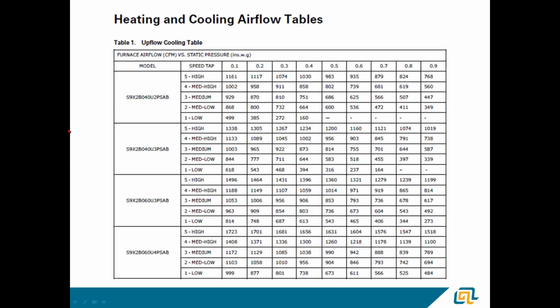This is a chart from the new S9 X2 furnaces. So these are the S series furnaces, the short cabinet 90%ers with the CTM, or the constant torque motor. The reason I have this up here is I wanted to show you, over here at your 0.5 static column where the blowers are rated, this particular furnace, 60,000 BTU, has a 3-ton drive. On high speed at 1/2 inch of static, we're moving 1,360 CFM. So we're actually a little bit over aired for a 3-ton.